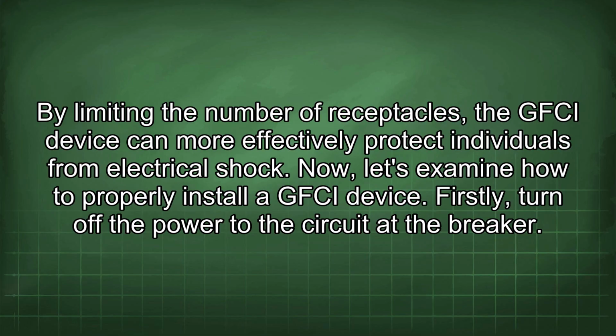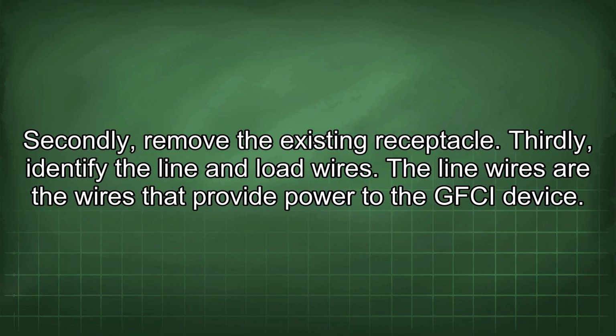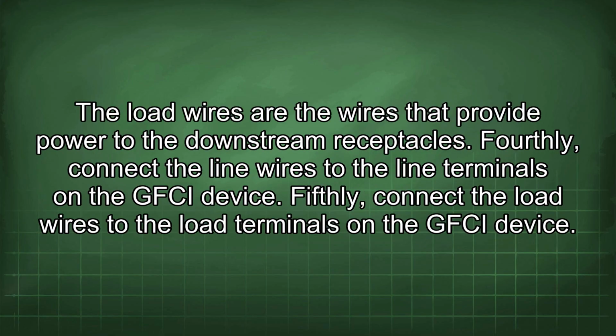Firstly, turn off the power to the circuit at the breaker. Secondly, remove the existing receptacle. Thirdly, identify the line and load wires. The line wires are the wires that provide power to the GFCI device. The load wires are the wires that provide power to the downstream receptacles. Fourthly, connect the line wires to the line terminals on the GFCI device. Fifthly, connect the load wires to the load terminals on the GFCI device.